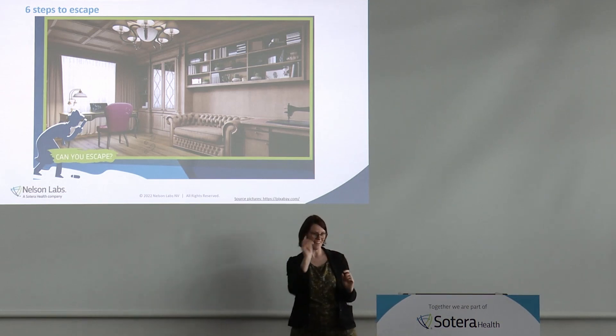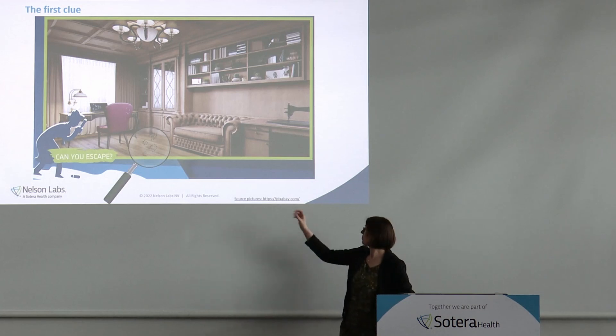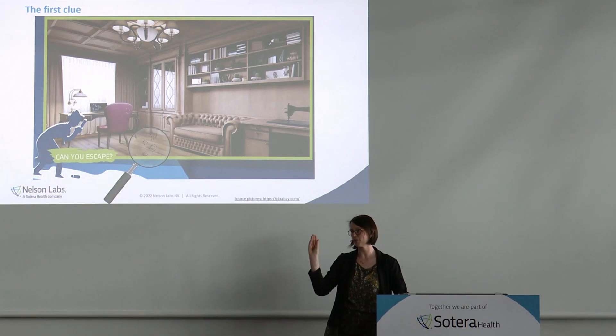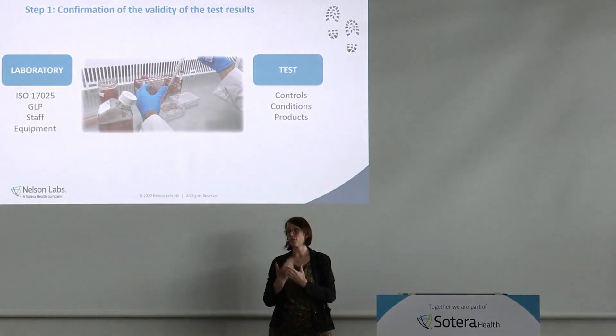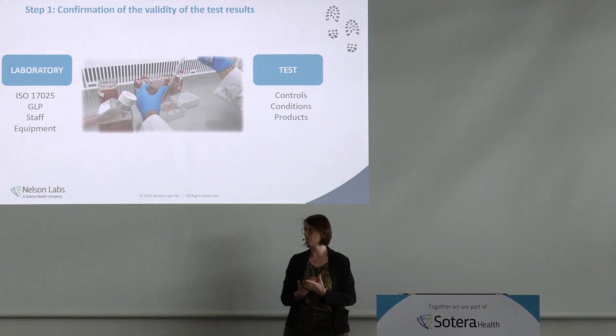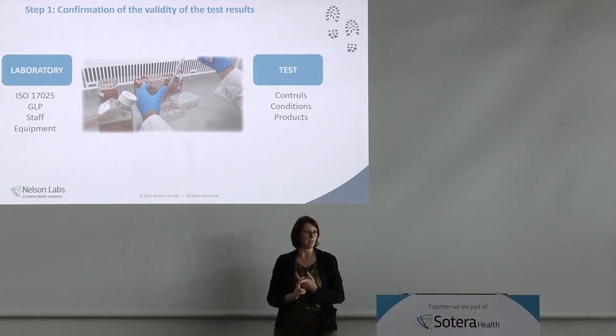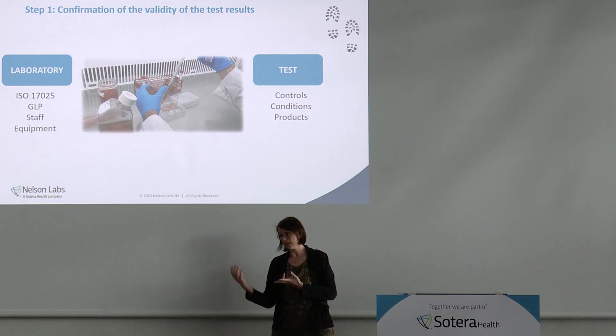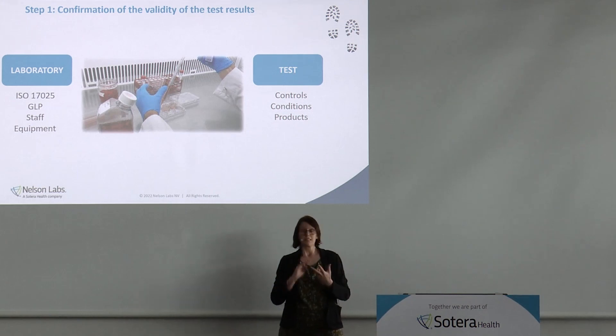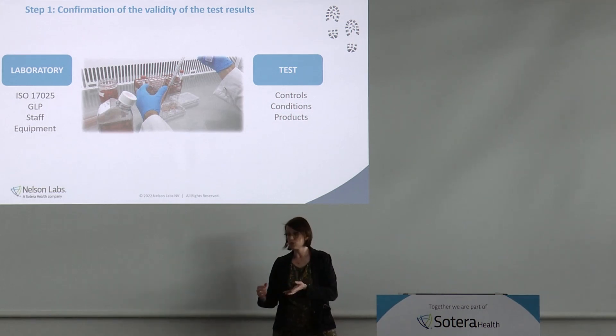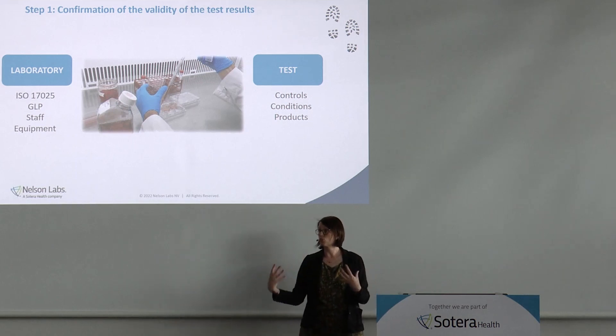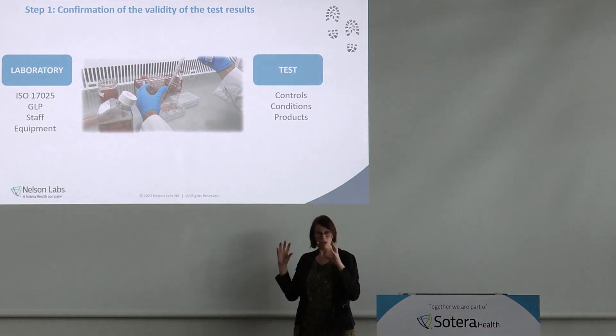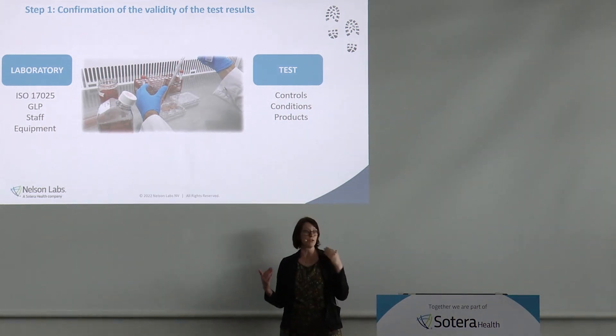Look at the floor — the footsteps. First clue found. Step one in your investigation is the confirmation of your laboratory results. You have to make sure the results you obtained are valid. Is the testing done according to the procedure? How is the lab accredited? ISO 17025 gives you a good idea. Is the staff trained? Are unexpired products used? Which controls are used? Which conditions were used for the extraction?